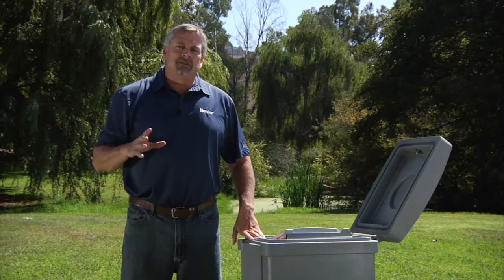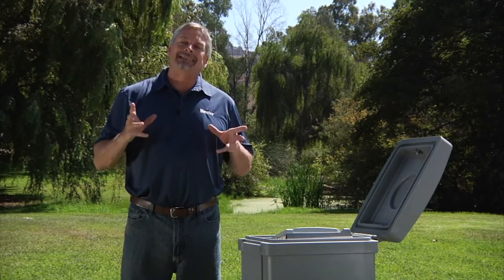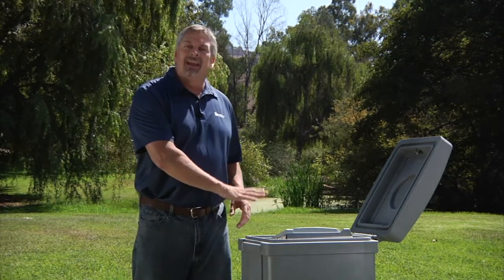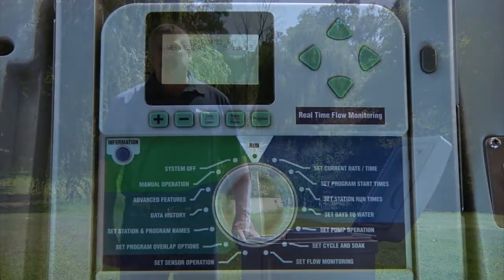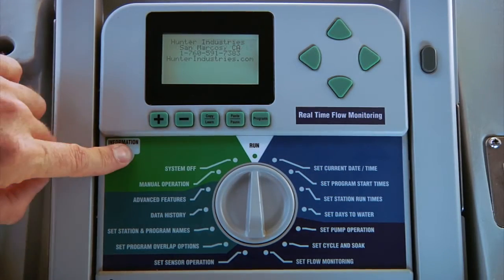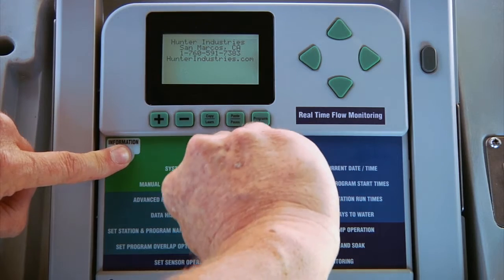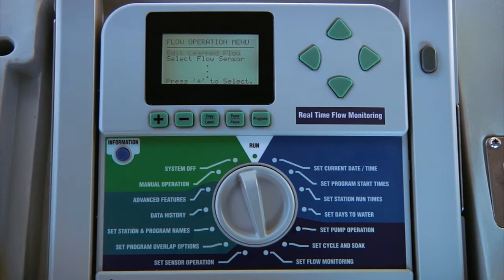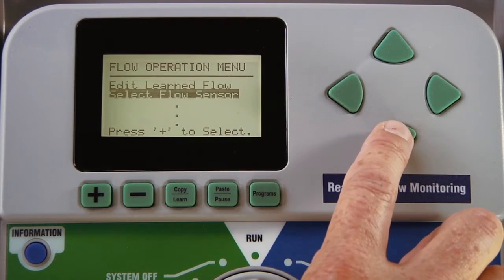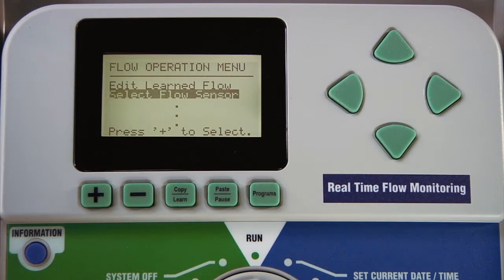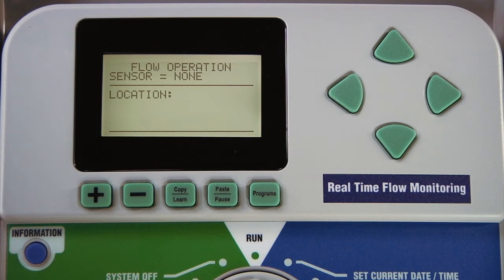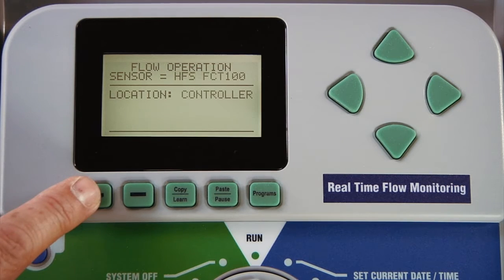Once the flow sensor is physically installed in the field, the next step is to configure the sensor in the controller. With the dial in the run position, hold down the blue information button and turn the dial to set flow monitoring. Release the blue button to unlock the flow operation menu. Use the down arrow button to select flow sensor and use the plus to access it. Here is where we'll be choosing which flow sensor size it is we have installed in the field.